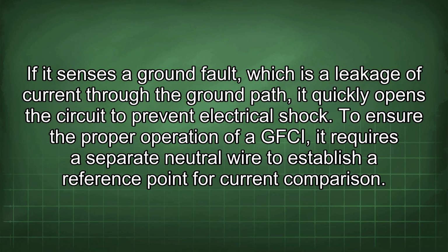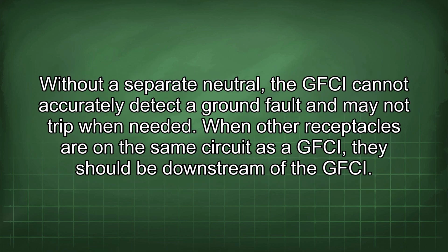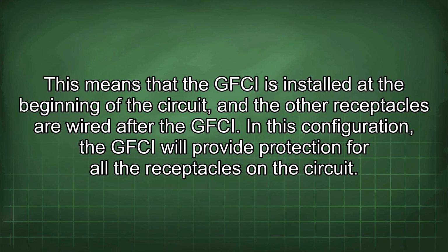To ensure the proper operation of a GFCI, it requires a separate neutral wire to establish a reference point for current comparison. Without a separate neutral, the GFCI cannot accurately detect a ground fault and may not trip when needed. When other receptacles are on the same circuit as a GFCI, they should be downstream of the GFCI. This means that the GFCI is installed at the beginning of the circuit, and the other receptacles are wired after the GFCI. In this configuration, the GFCI will provide protection for all the receptacles in the circuit.